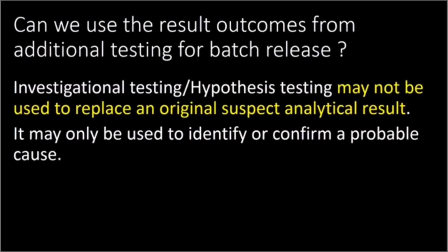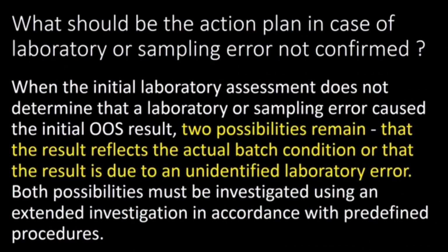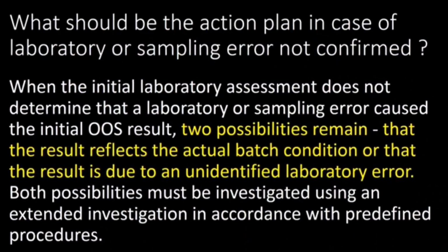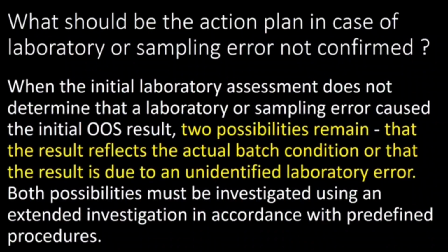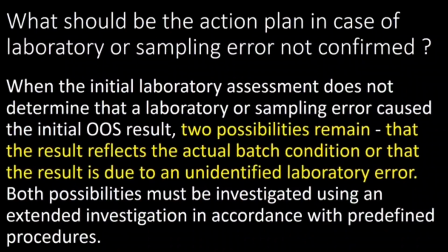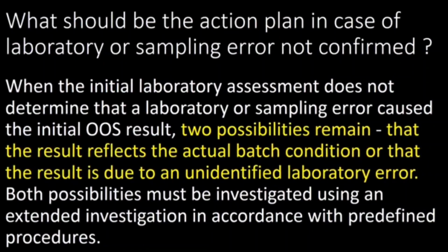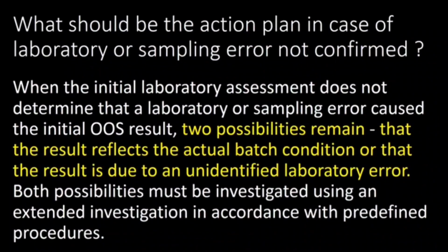Can we use the result outcomes from additional testing for batch release? Answer is no. Investigational testing or hypothesis testing may not be used to replace an original suspect analytical result. It may only be used to identify and confirm a probable root cause.